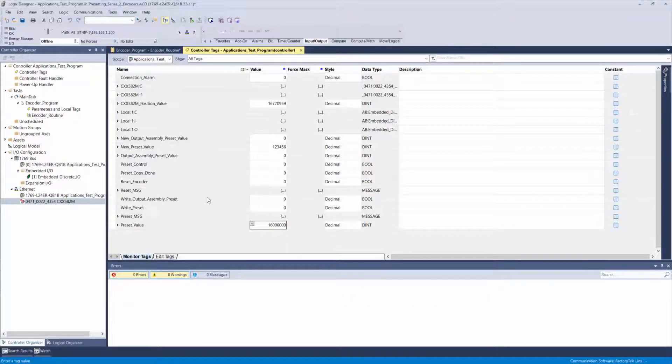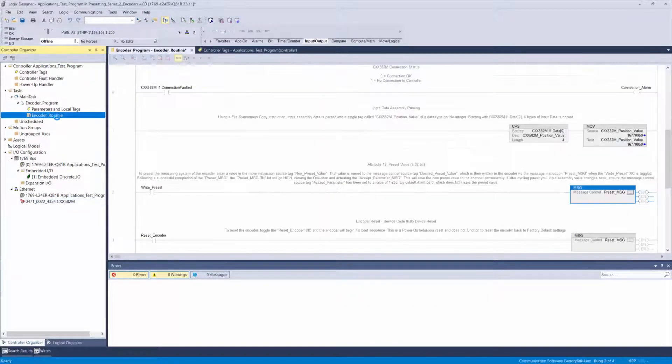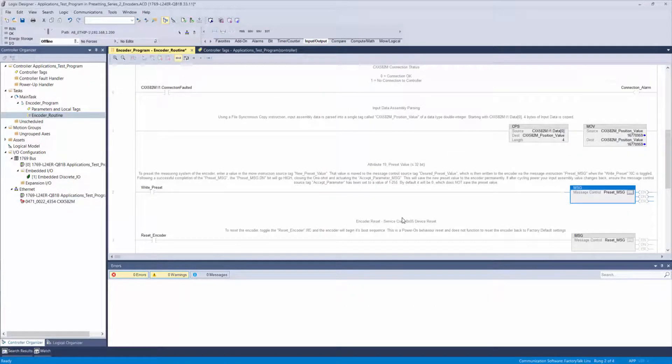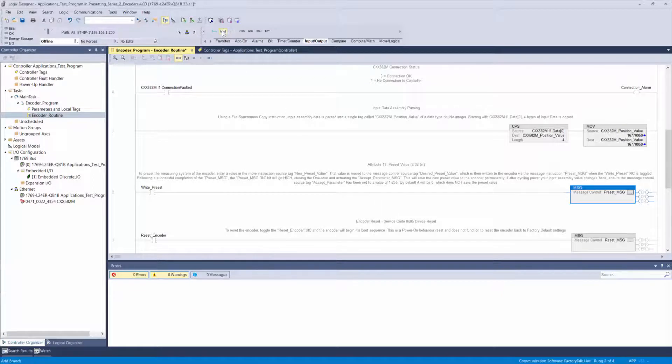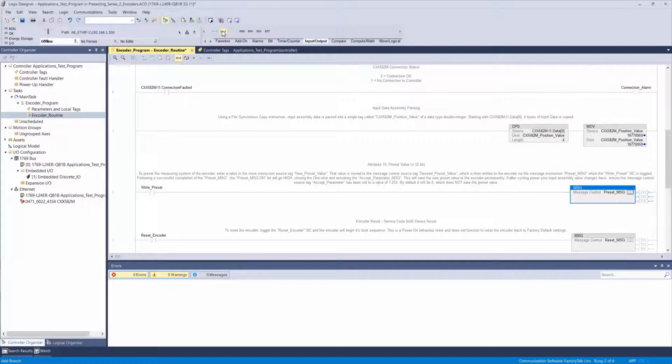Our next step is to create our accept parameter message which will save the value to the encoder. If you do not do this step and power is cycled to the encoder, any previous preset value that was applied will be lost.